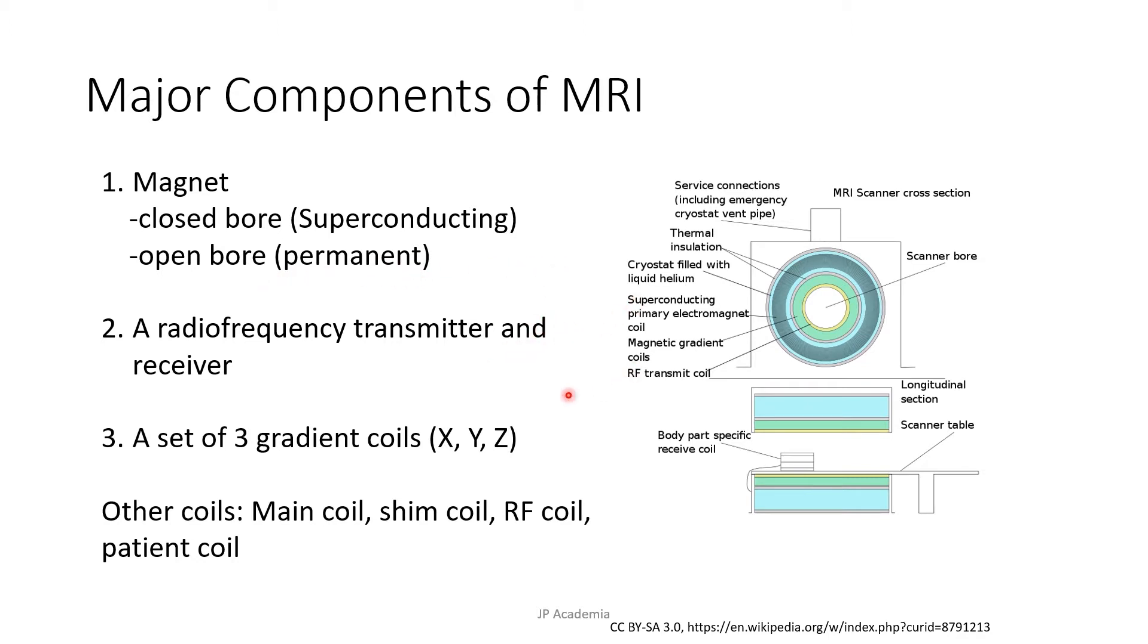There are different types of coils in MR. First, we have the main coil, which produces the B0 or the magnetic field. We have the shim coil, which improves the homogeneity of the magnetic field. We have the gradient coil, which is for imaging, and we have three gradient coils for this case.